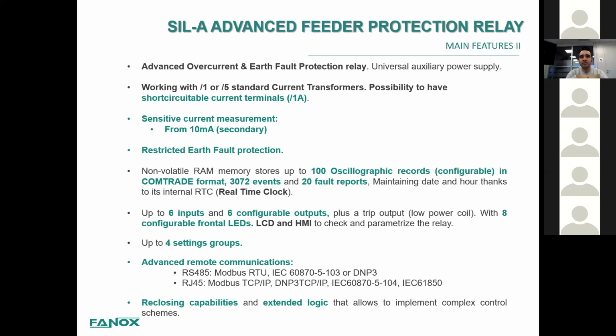And regarding the events recording, we can go up to 100 oscillography records in COMTRADE format, 3,072 events, and 20 reports. As you can see, the storage of this relay is much bigger than the previous ones. And we also have up to 6 inputs and 6 configurable outputs with 8 configurable frontal LEDs. Again, LCD and HMI to check and parameterize the relay.